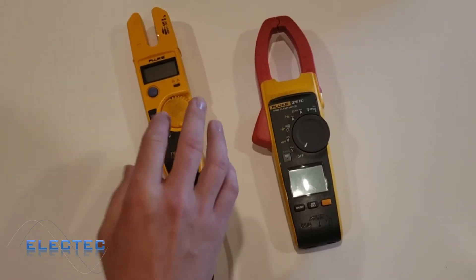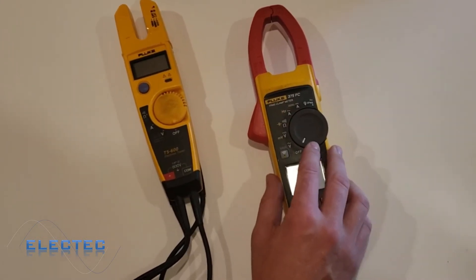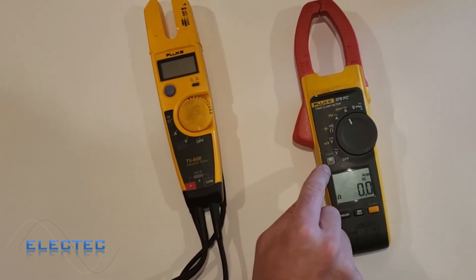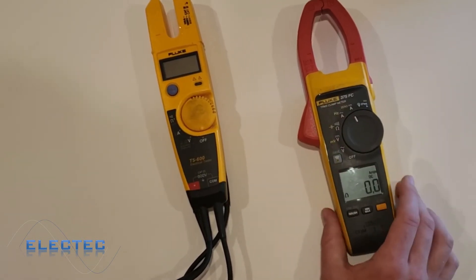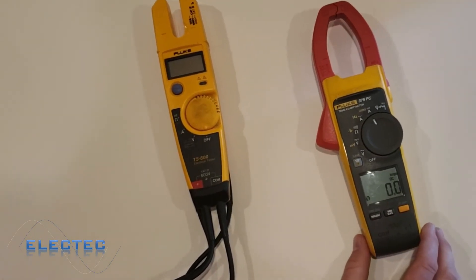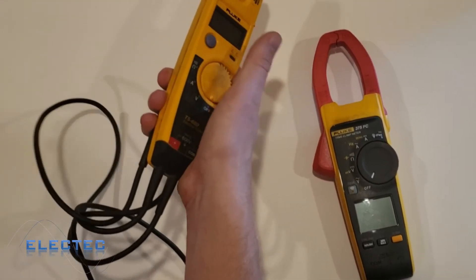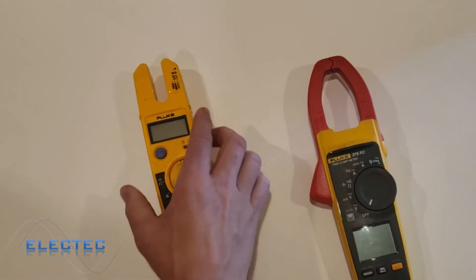To summarize: we went through the Fluke T5-600 and the Fluke 375 FC. In my opinion, the 375 FC is by far the superior meter — it shows more precision, has more options, and can read higher resistance values. Another option this particular meter has is Fluke Connect, which means you can download an app and graph and monitor the actual current over Bluetooth from your phone. There's also the hold button: if you're measuring something and can't see the screen, just hit hold, pull the meter out, and see what it said.